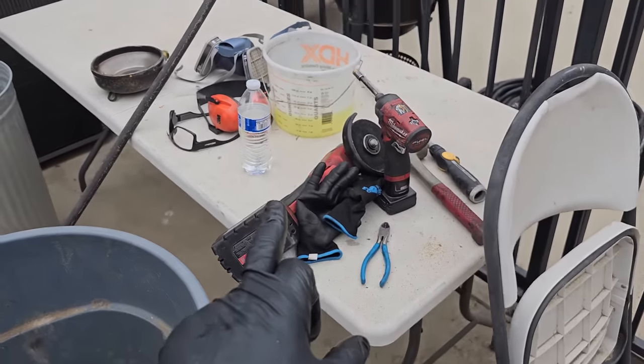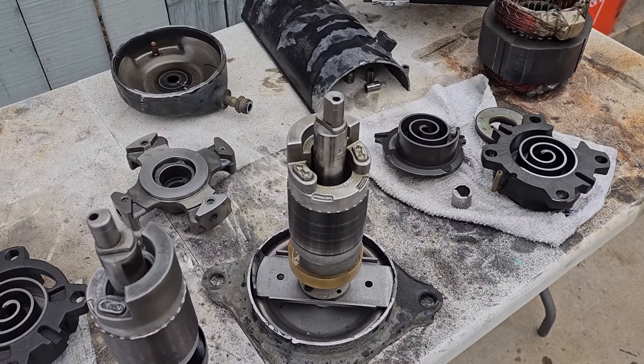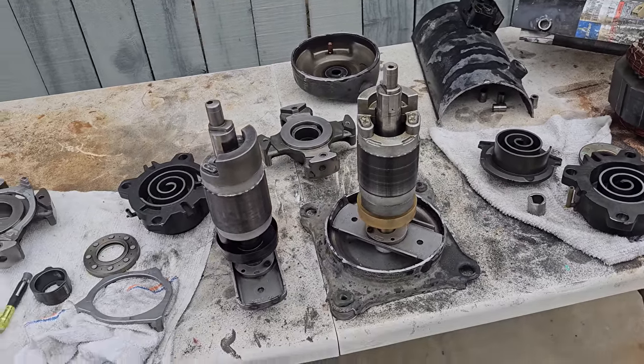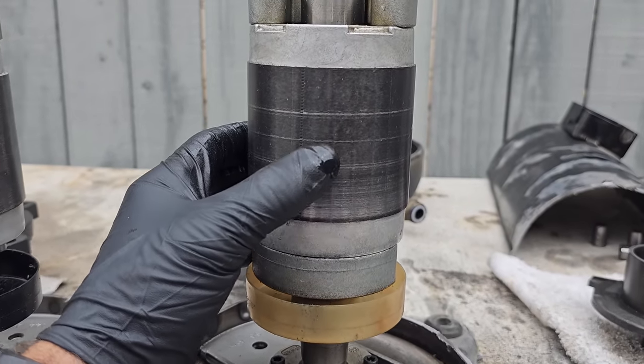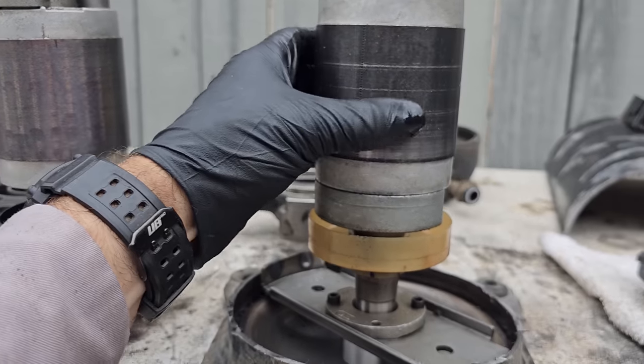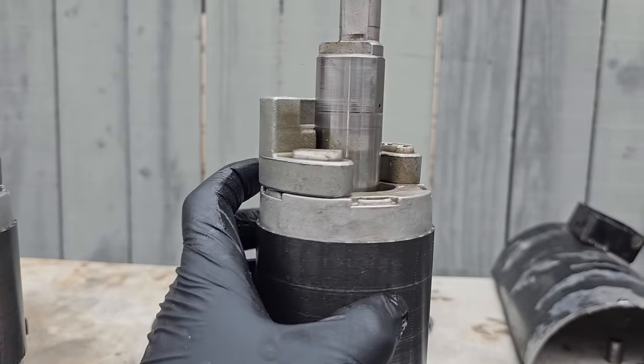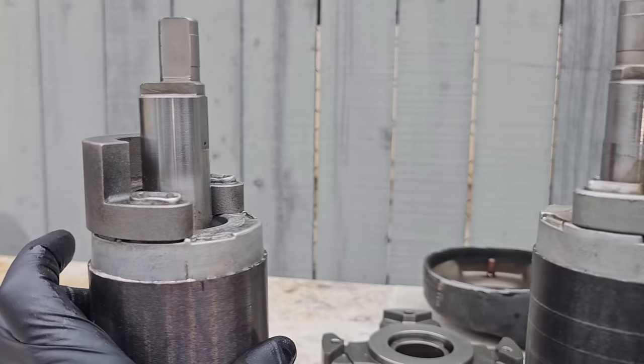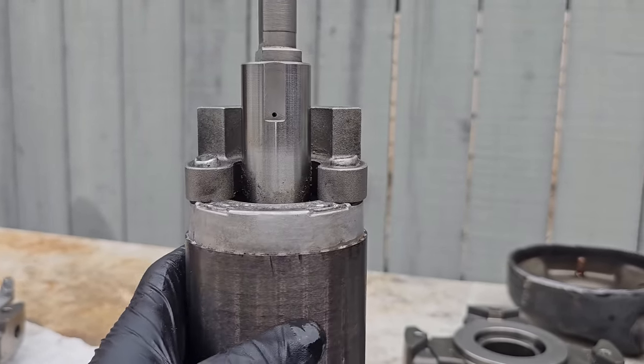Now, we were a little bit shy on oil, but I don't think it was enough to cause an issue. We could have had an oil return problem in the past. See, I originally thought that's what we were going to find. Look at the wear pattern right here compared to this one. Yeah, that's very, very interesting. And then look right here. Look at that, compared to this one. Now remember, this one was an electrical failure, not a mechanical failure.